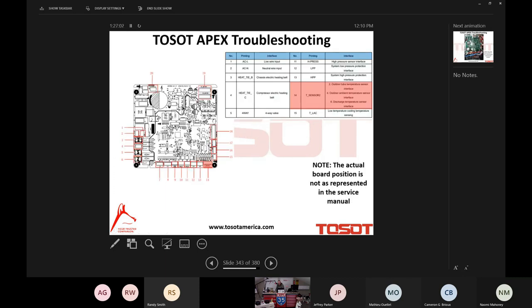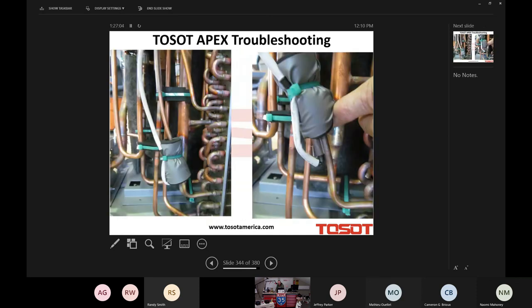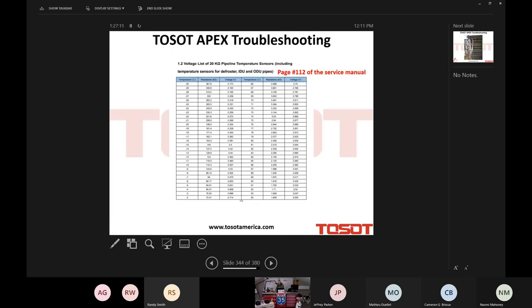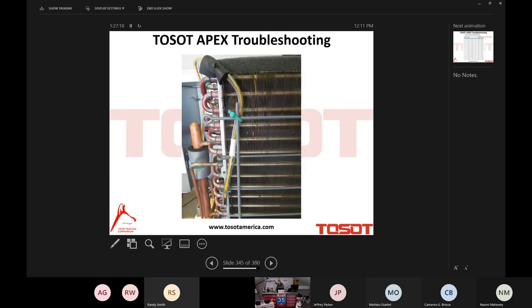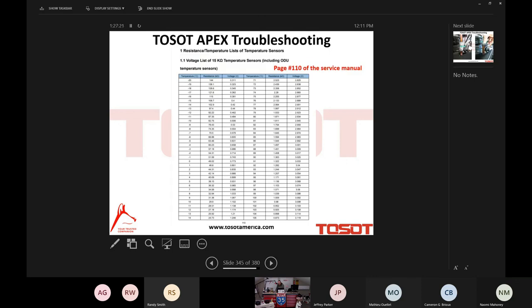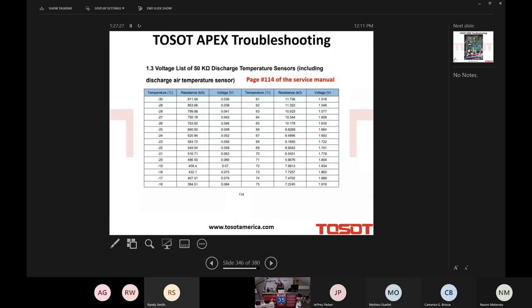There they are. I showed you this slide earlier. There they are coming off the main control board. There is your outdoor heat exchanger sensor, and there is your resistance chart for it on page number 112 of the service manual. There's your outdoor ambient temperature sensor. That is a 15K sensor, and its resistance values are on page 110. And lastly, the discharge temperature sensor, a 50K sensor, and those values are stated beginning on page 114 of the service manual.